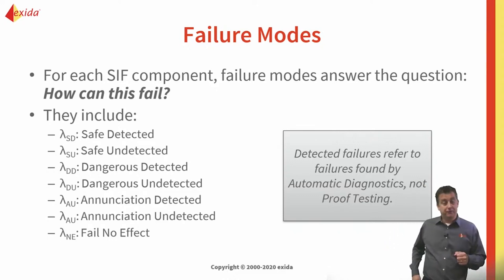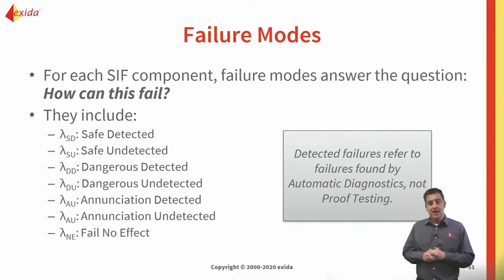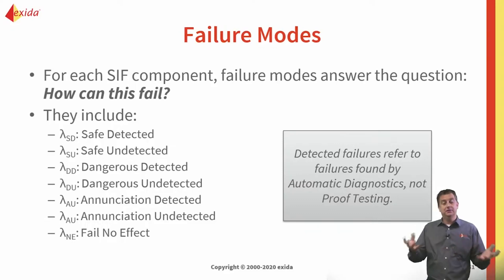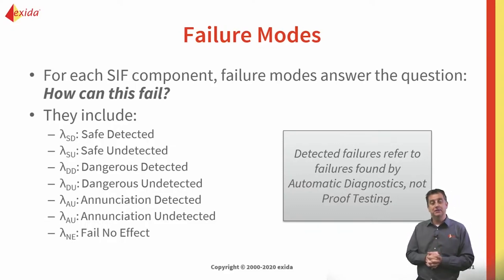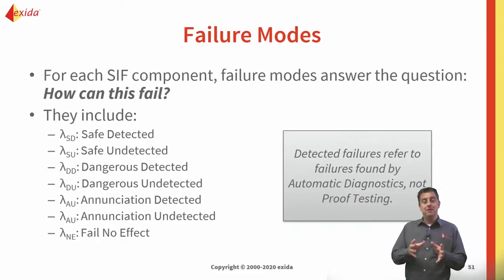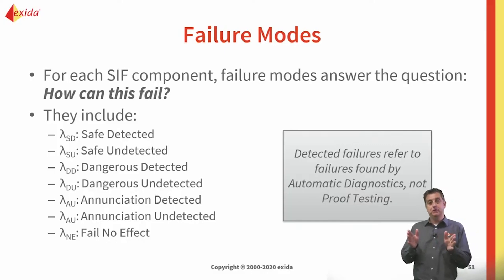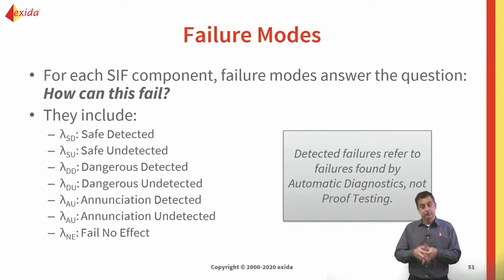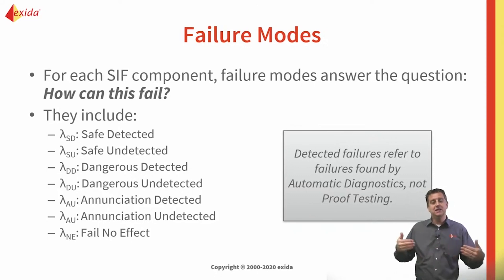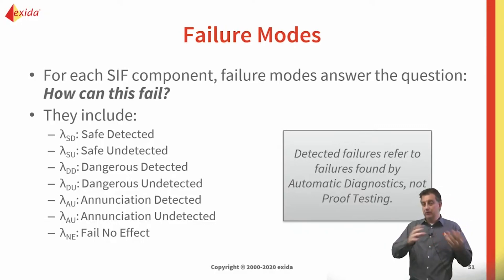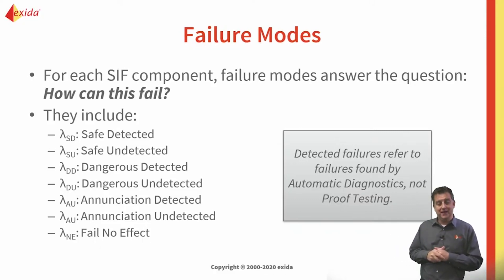Safe and dangerous failures are further divided into detected and undetected failures. 'Detected' refers to the ability of self-diagnostics within the safety function to reveal a problem occurring at one of the components. An example would be implementing partial stroke testing on a valve — a dangerous failure like a stuck stem would be revealed because you'd see that the valve doesn't move. Other failures, like seat issues, would not be detected because you're only doing a partial stroke. Different diagnostics have different levels of effectiveness.